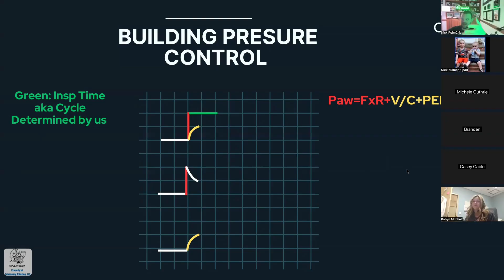So at the end of inspiration, your alveolar pressure will go up until it meets your airway pressure. Once it meets your airway pressure, your alveolar pressure, which is this yellow line, equals your airway pressure, which is this white line, which I've sort of put together as this red dot. Because the pressures equalize, the flow stops, so this flow goes to zero, and then you've delivered some volume based on the resistance and the compliance. Okay? So that's an important concept.